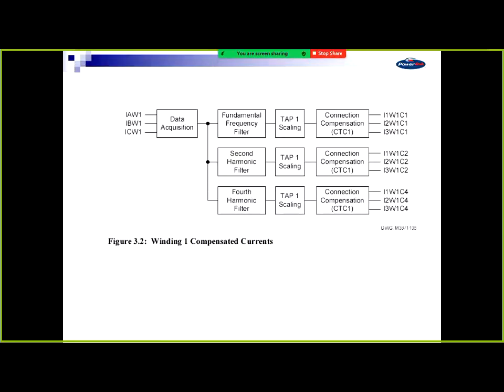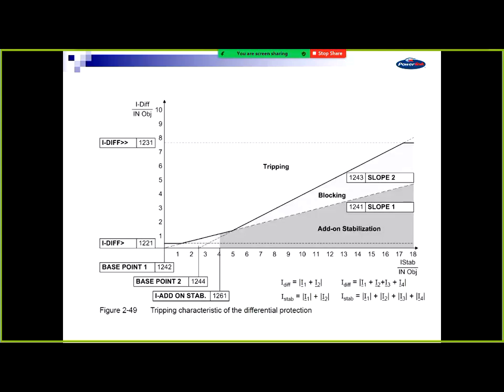So this is, you've got your data acquisition. This is how it looks like. You've got some fundamental frequency filters, 2nd and 5th harmonic, what your tap settings are, scaling for that, and then you've got that compensation that we just went through, and you come out with a compensated current that they use to compare their bias diff. It's basically how the internals work.